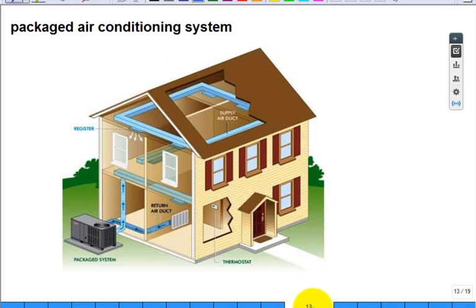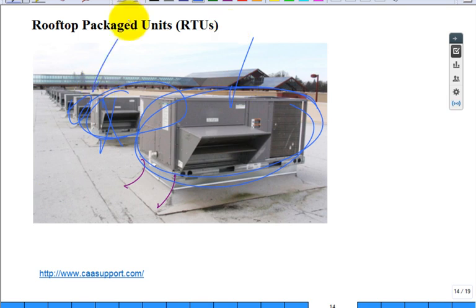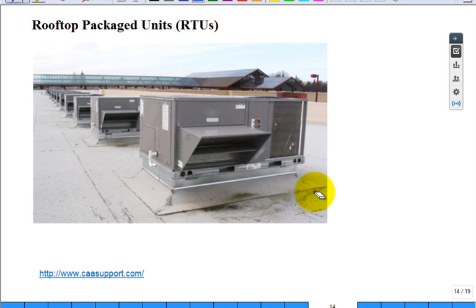Sometimes you'll see a package unit, meaning all the refrigerants out here. No refrigerant line set takes in or out of the house. There's no indoor unit. What they do is they bring all the air outside and then they return all the air. If they retrofit a house that has a basement, they may use a packaged unit that's sitting outside. But they're rare. But you can see those. What you see a lot of in the commercial world are rooftop packaged units. So here, the refrigerants in this isolated package. That package could have a problem with it and go out of service. The other ones would still run and the whole system wouldn't go down. If in your house you have a problem with a compressor, your whole house suffers. But if you have a bunch of rooftop units in a commercial building, big Sam's warehouse, Walmart, whatever, big Lowe's, Home Depot type of big supermarket, they can service one while the other ones are still functioning.